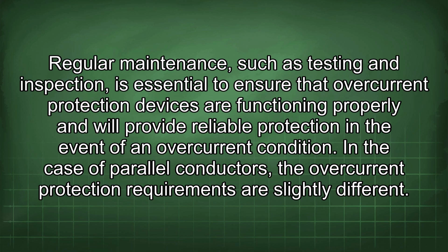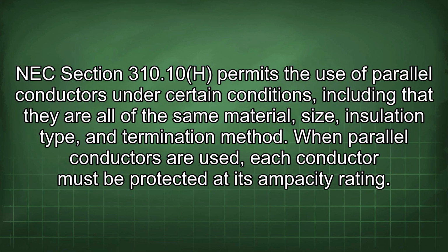In the case of parallel conductors, the overcurrent protection requirements are slightly different. NEC Section 310.10(H) permits the use of parallel conductors under certain conditions, including that they are all of the same material, size, insulation type, and termination method. When parallel conductors are used, each conductor must be protected at its ampacity rating.